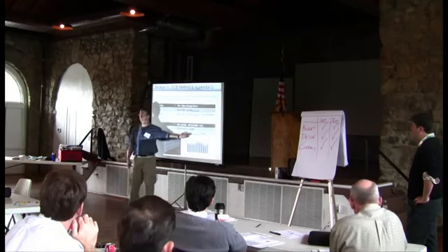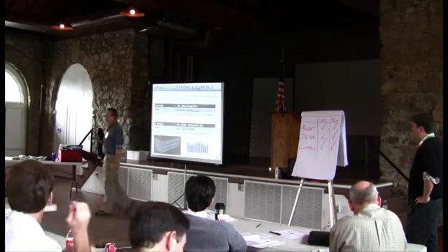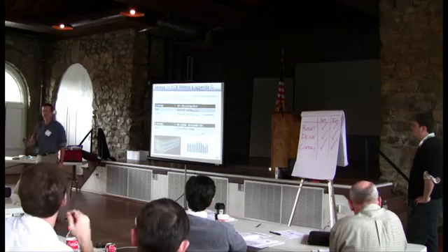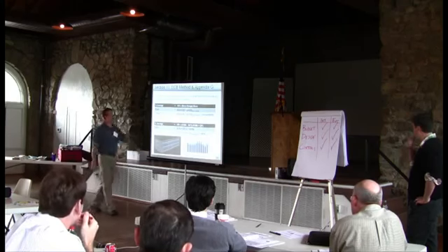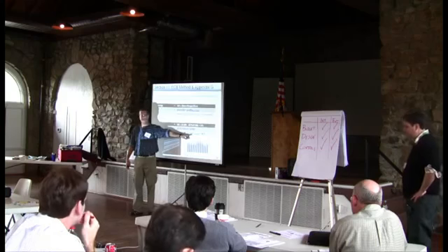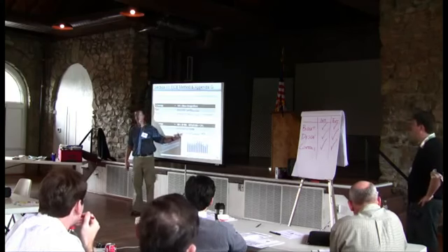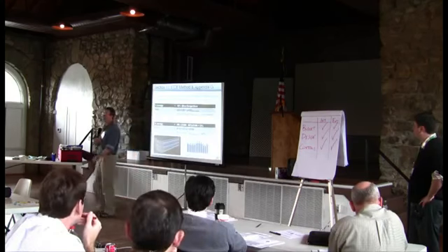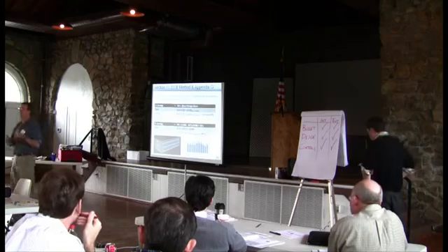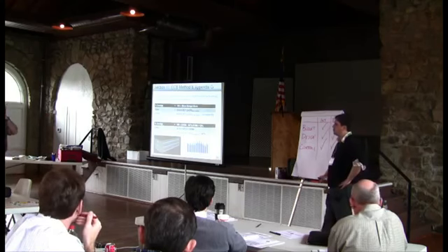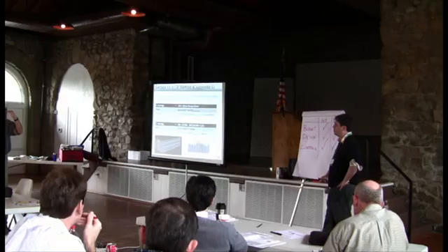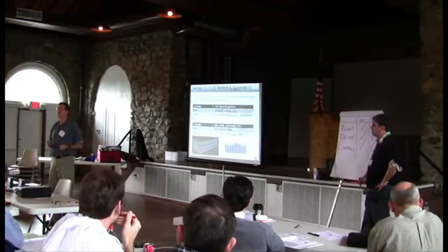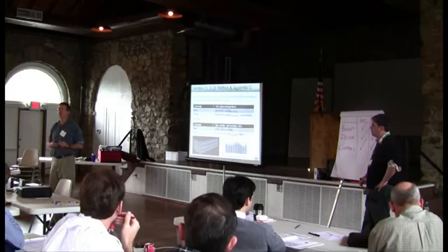And if you have a system that will, let's say, create $3,000 worth of renewable energy, it could be photovoltaics, it could be solar thermal, but in essence, I'm generating the value of energy in a year's time that's worth $3,000. That subtracts off my bottom line. So now instead of 70, I'm at 67,000. So my building, as I'm designing it, would use $67,000 a year versus the base case, just meeting code, would use $100,000. That's a 33% improvement over the code. I beat the code by 33%.